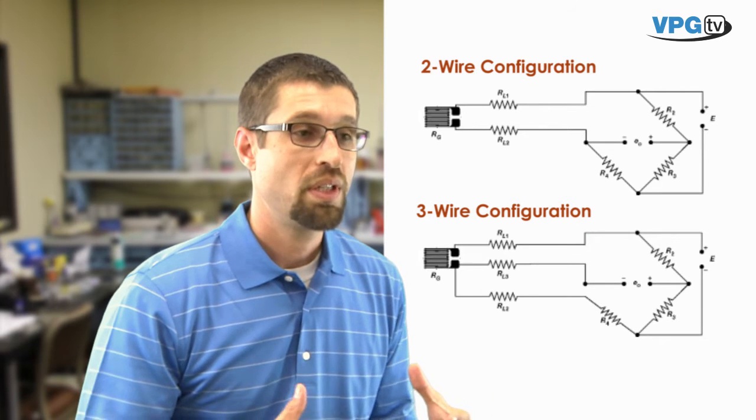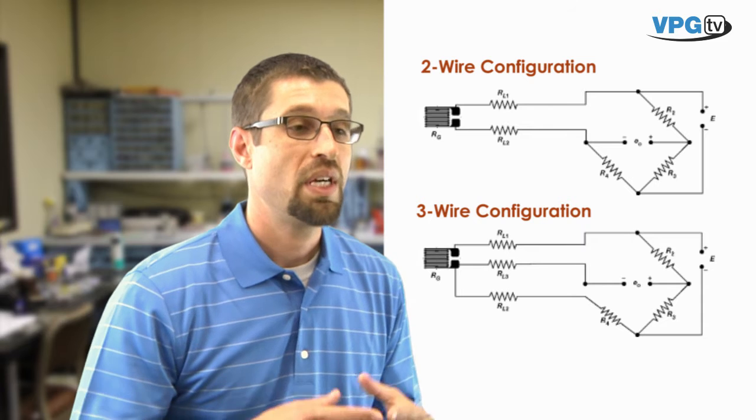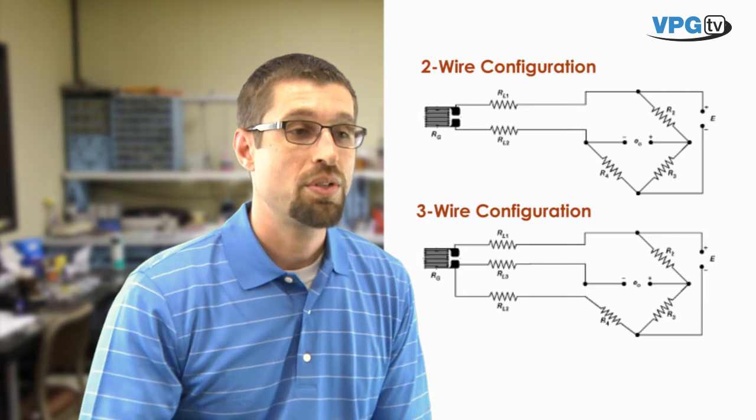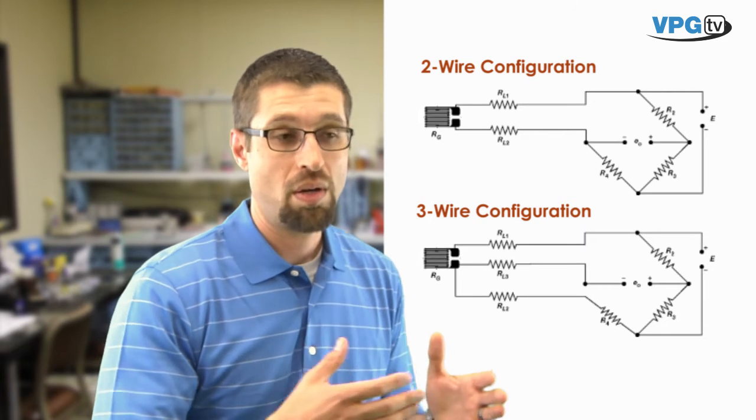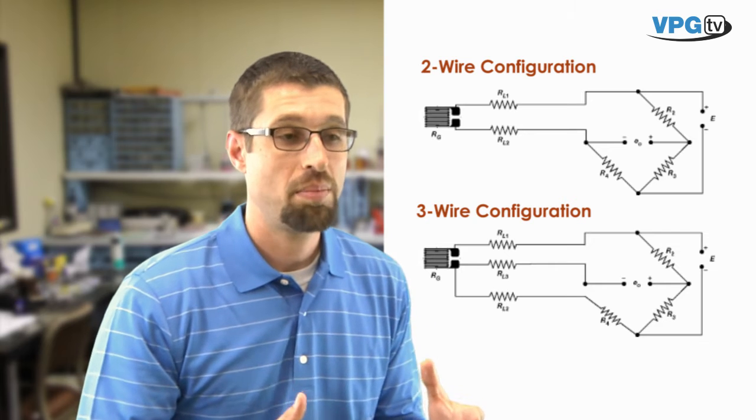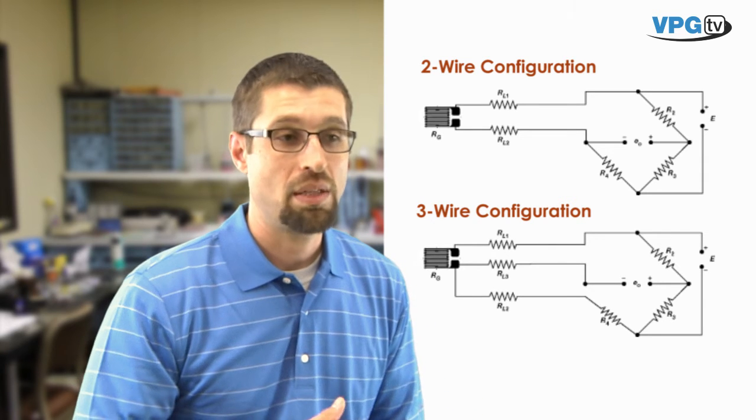The first thing that a two-wire configuration does is that it generates initial offsets in your reading, some of which could be so large due to the amount of lead wire length that you have that your instrumentation may not be able to balance those out.